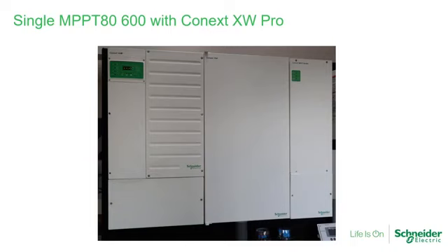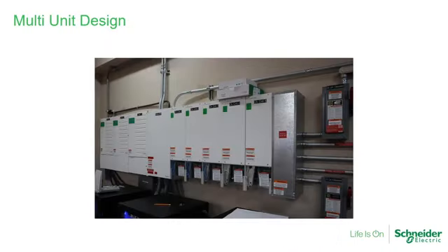It lines up perfectly to one of the sides of the PDP. And the knockouts here match exactly to the side of the MPPT80. So you can run your PV as well as your battery cables. Here's another photo of a real system, and this system has 5 MPPTs and 3 of the Conext XW inverters.